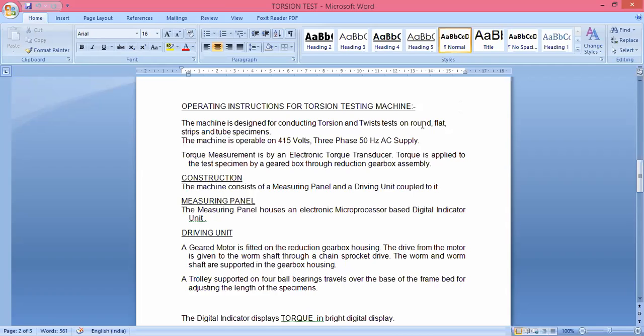Now, this torsion or torque is measured by an electronic torque transducer. It transforms the torque by means of the transducer into a different amount of force required to make this type of twist. The torque is applied by a geared box, which I've just shown you, through a reduction gearbox assembly.